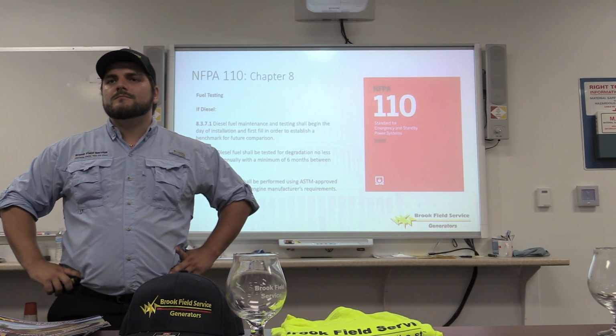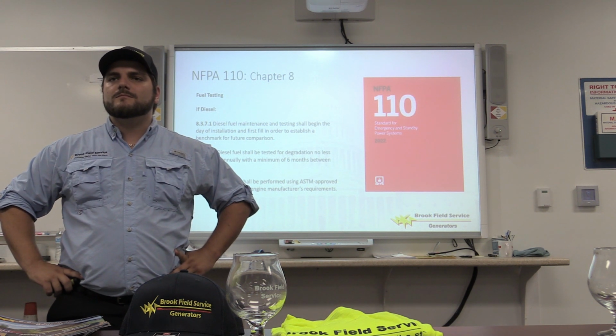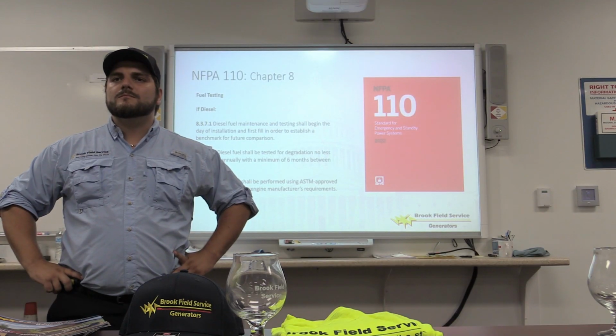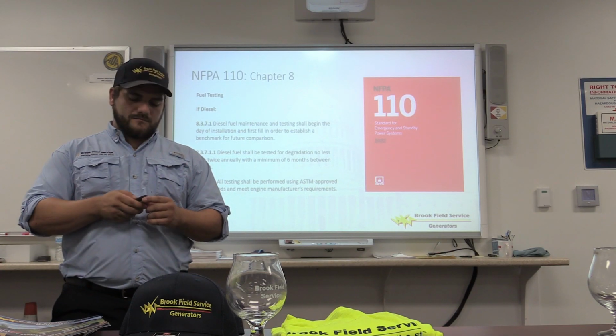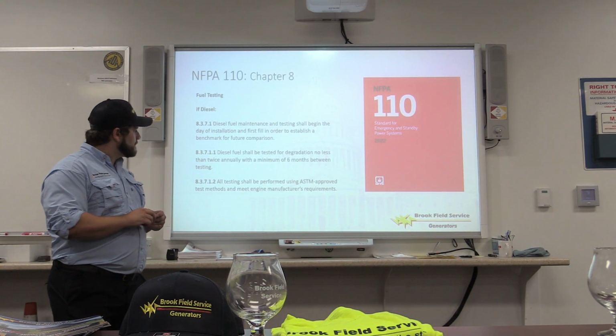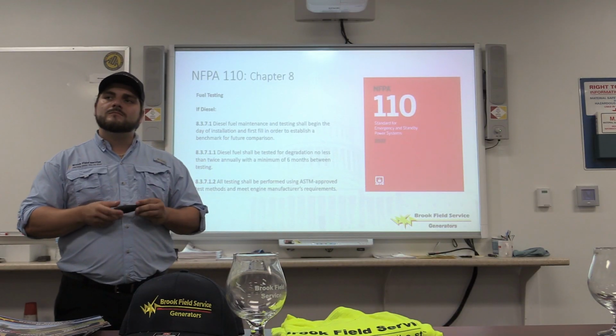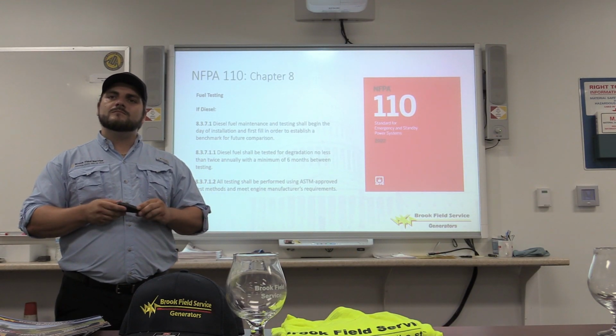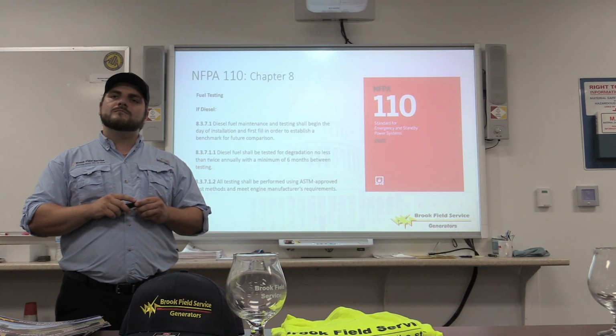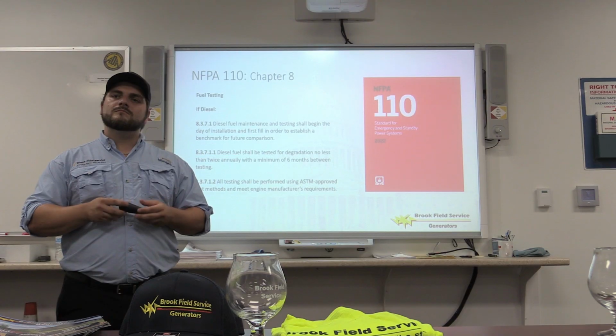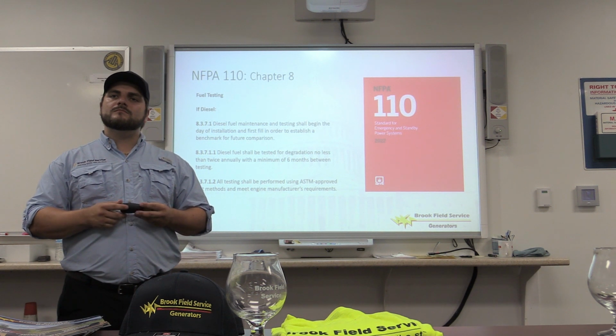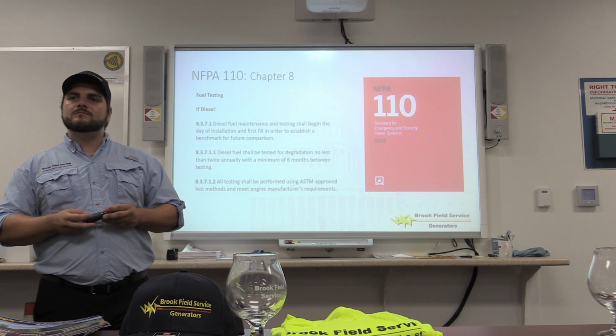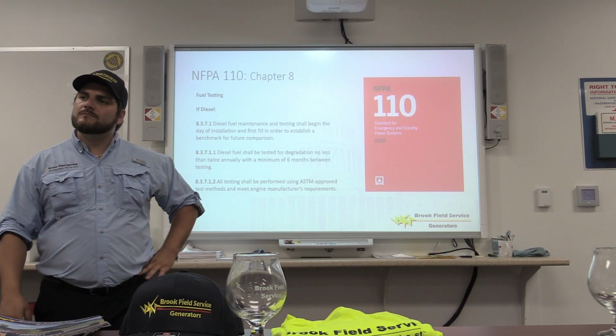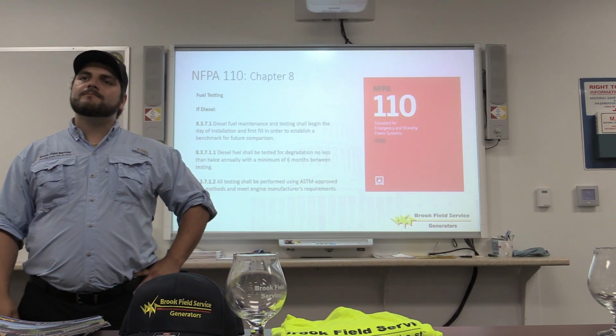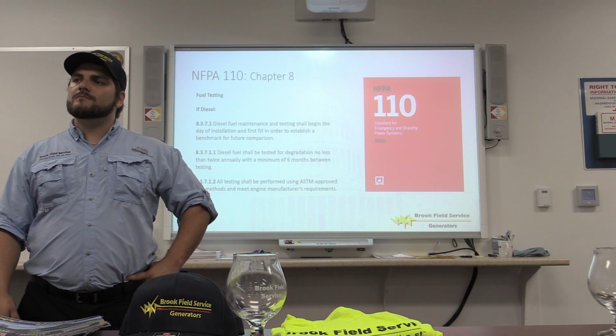The fuel no longer having the sulfur, and you get condensation in the tank, you get water. Nursing homes now are requiring 72-hour tanks, and that's a lot of fuel sitting there. They'll never use that in a year, so they're gonna be subject to someone coming in and doing a fuel polishing situation. Does that happen with both gas and diesel? No, it's just related to diesel fuel. The propane, there's no issue.